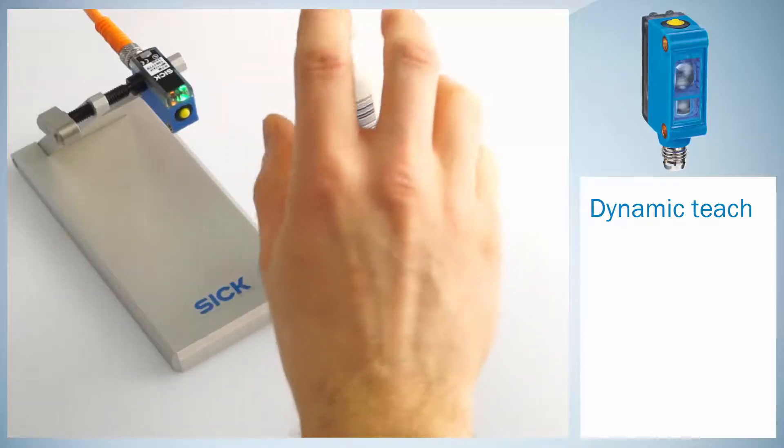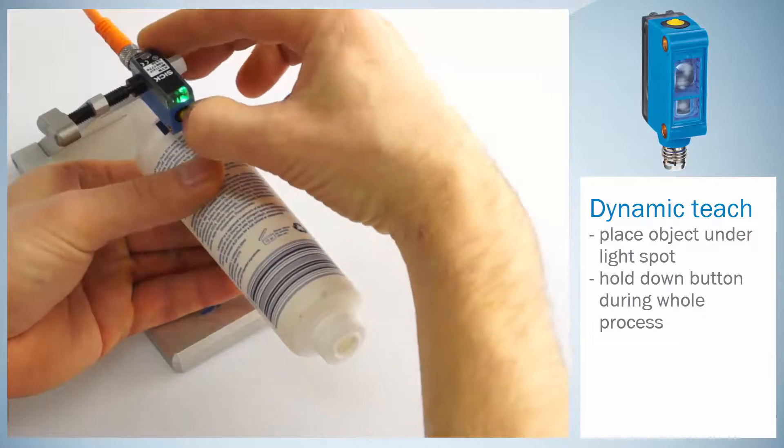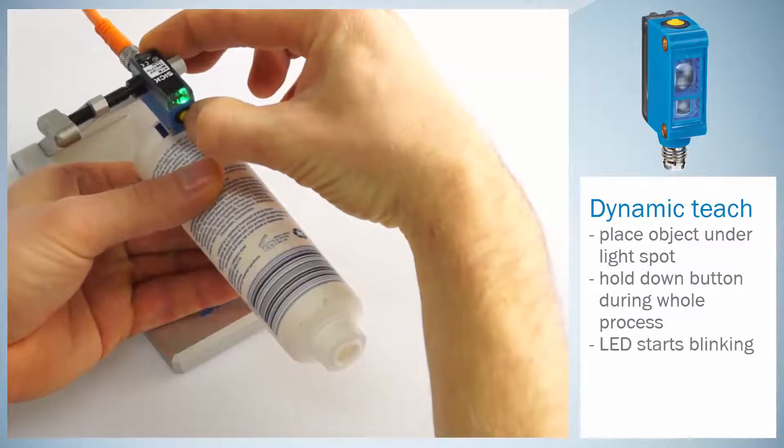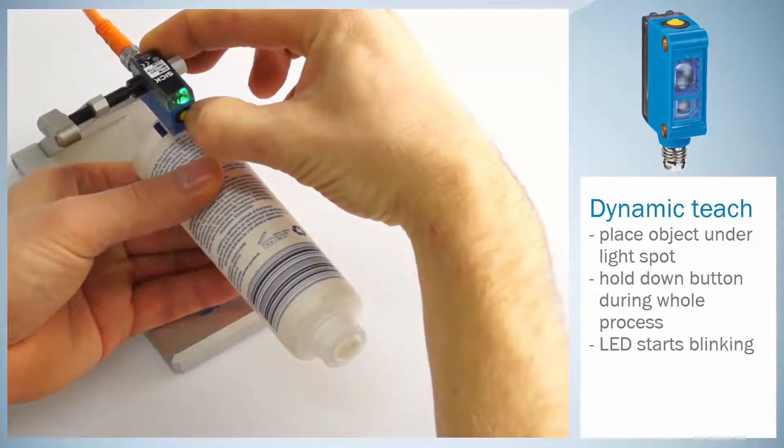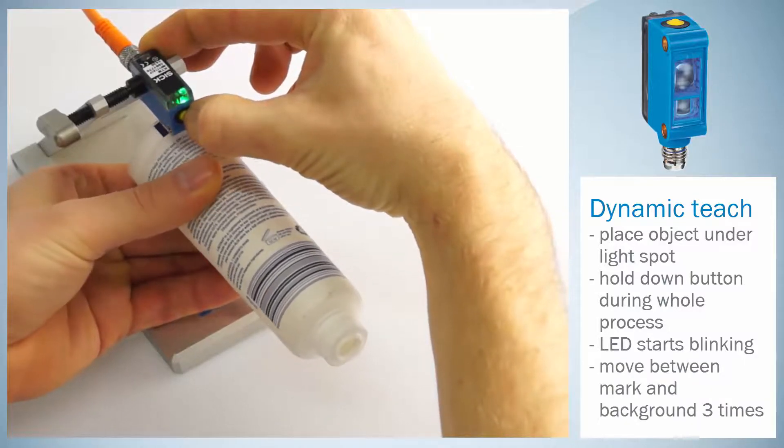For the dynamic teach-in, place the object under the light spot and hold the teach button down for the whole process. After three seconds, the LED starts blinking. Now move the material between mark and background for at least three times.